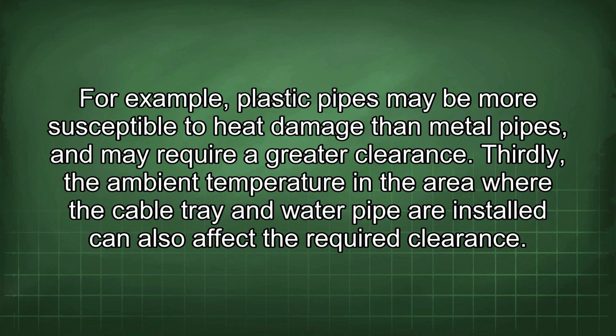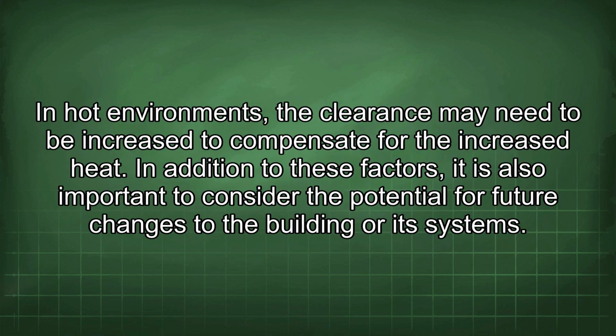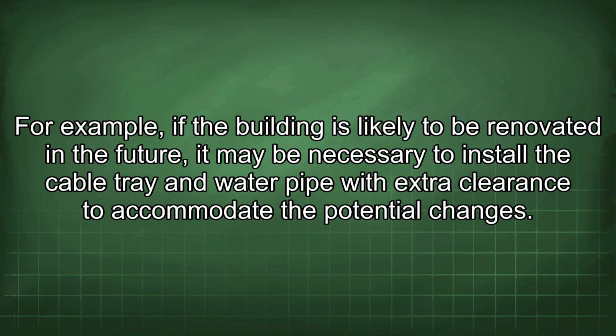Thirdly, the ambient temperature in the area where the cable tray and water pipe are installed can also affect the required clearance. In hot environments, the clearance may need to be increased to compensate for the increased heat. In addition to these factors, it is also important to consider the potential for future changes to the building or its systems. For example, if the building is likely to be renovated in the future, it may be necessary to install the cable tray and water pipe with extra clearance to accommodate the potential changes.